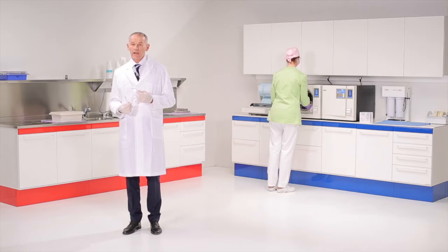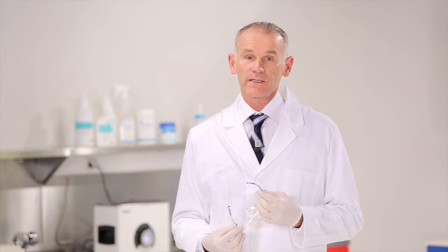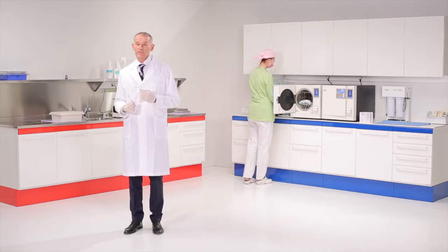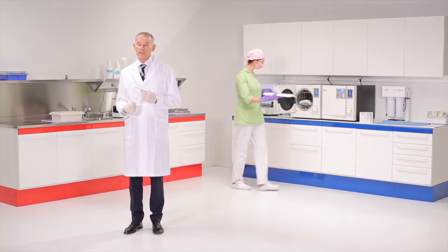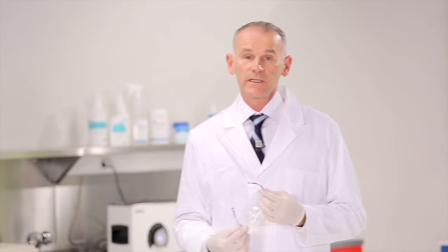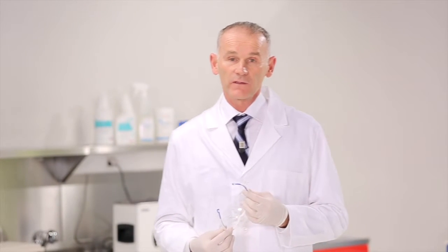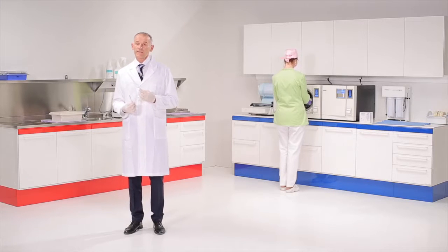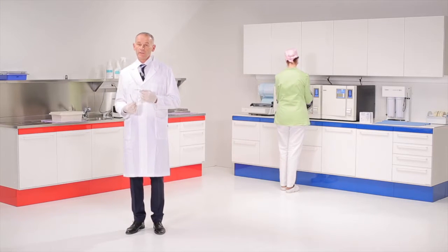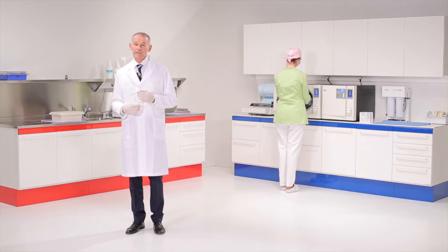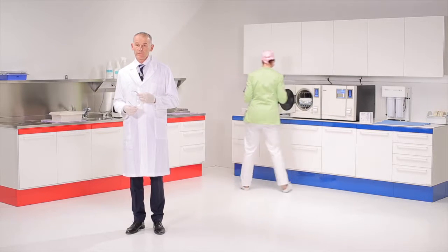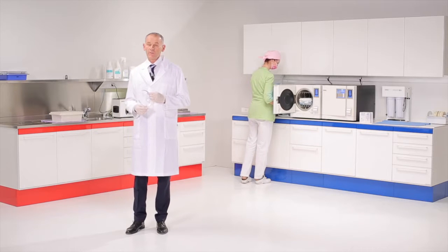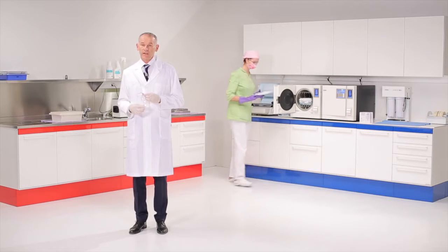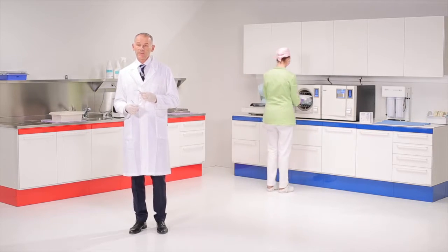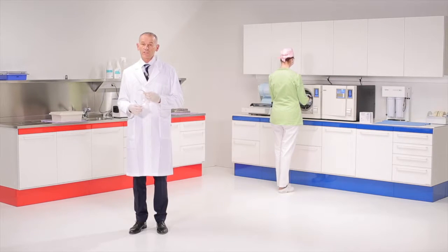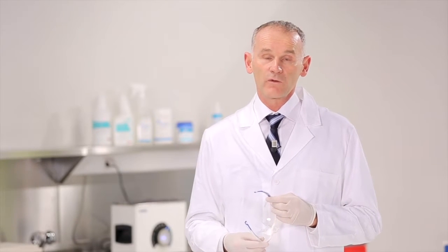We must keep in mind that we can only sterilize dry, clean instruments. The sterilization stage will be carried out with a saturated steam autoclave, the only technology currently allowed in dental practices. The purpose of sterilization is to eliminate all microbial forms, pathogenic or otherwise, including spores and fungi. The assistant places the bags in the autoclave tank, ensuring the paper of the bag faces upwards in order to facilitate the penetration of water vapor and sterilizing agent, then continues with the drying.